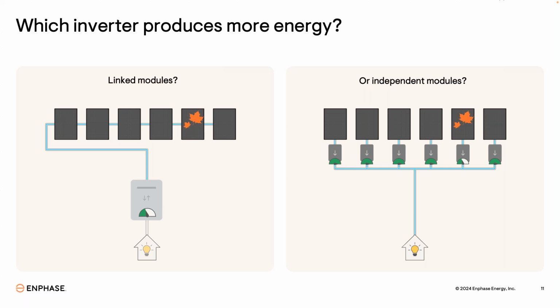We're bringing this up because of the entrance to the market of Powerwall 3, which is a hybrid inverter system where the inverter is built into the battery unit. They have done away with using MLPE, which was a shock to us and I think to many solar professionals, that they went that route. Since there are no microinverters, there is no optimization, so they are really susceptible to performance being impacted by shade on the system.